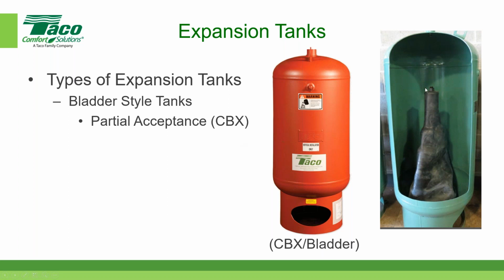But I will say that in our example, the steel container was 200 gallons, and we assumed the bladder could hold 50 gallons. If you try to put more than 50 gallons into the bladder, you run the risk of rupturing it. One advantage of a full acceptance tank is that the bladder holds the same volume as the steel container, so you can't rupture the tank by filling the bladder 100% with water. If you try filling the bladder of a partial acceptance tank beyond its acceptance volume - say, putting 70 gallons into a 50 gallon bladder - you run the risk of rupturing it. It will hold a little more than 50 gallons, but not dramatically more, and certainly around 70 or 80 gallons you risk rupture.